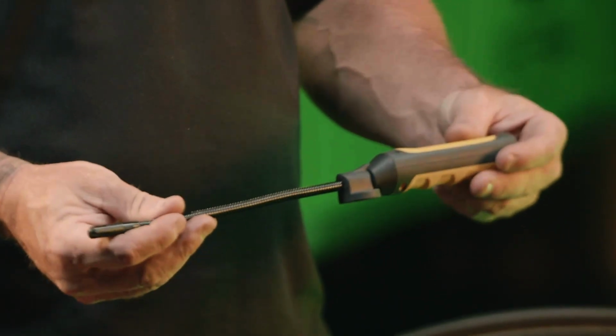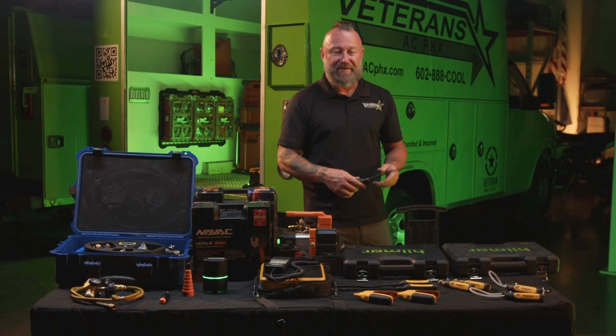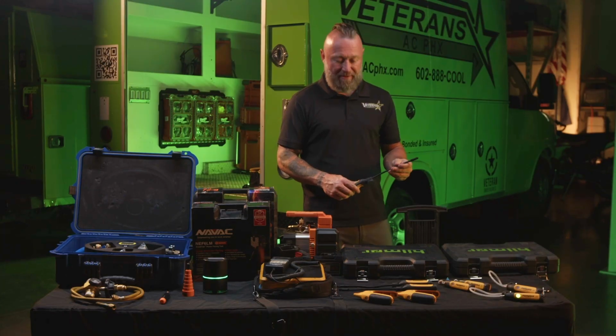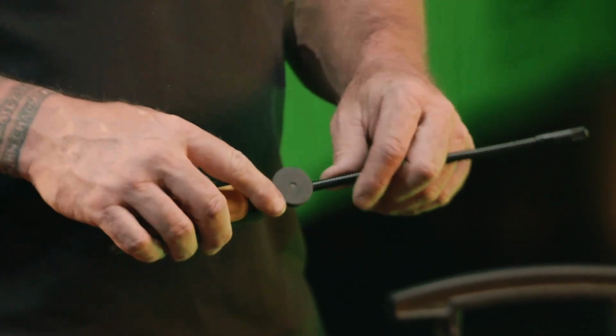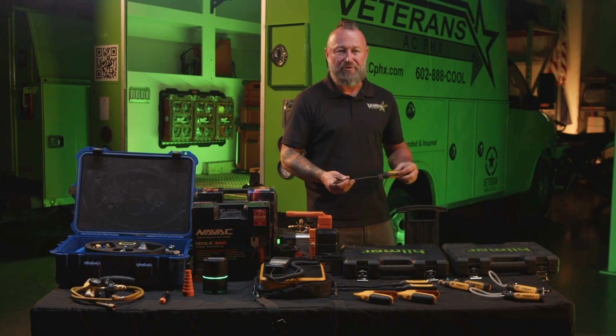So on our temperature probes, also called psychrometers, we're going to drill and tap the ductwork. We're going to throw one in the supply. We're going to put one in the return, and then we're also going to have another one outside of the unit, and that's more data collected that's going to go into our MeasureQuick system.